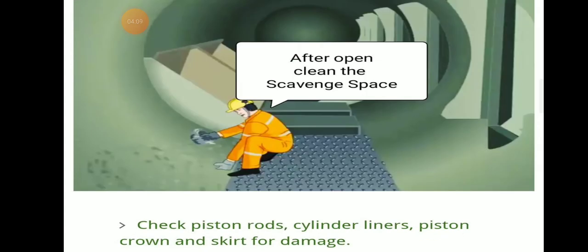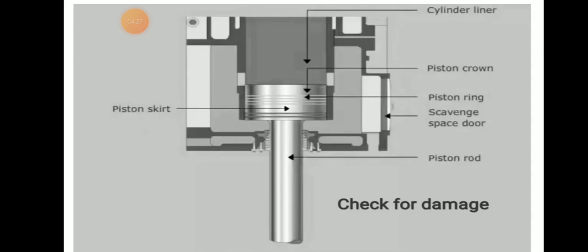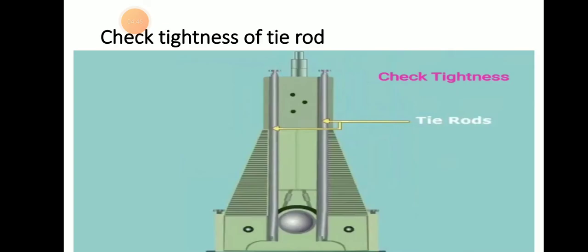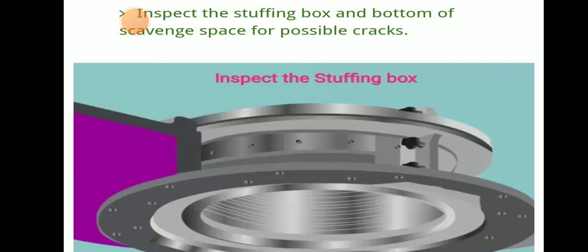After opening the scavenge space, clean it and remove all carbon and sludge deposits. Check the cylinder liner, piston rod, piston crown, piston skirt, piston rings, and scavenge space door for any damage. Also check the tightness of the tie rod, as distress or vibration may have occurred. Inspect the stuffing box and bottom of the scavenge space for possible cracks that could lead to another fire.